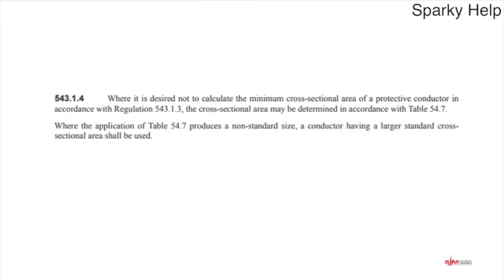Where it is desired not to calculate, and I think most of us would prefer not to calculate if required, the minimum cross-sectional area of the protective conductor in accordance with 543.1.3, the cross-sectional area may be determined in accordance with Table 54.7. Where the application of Table 54.7 produces a non-standard size, a conductor having a larger cross-sectional area shall be used. And I would say probably most electricians out there would know how to size an earth, and they probably won't need to look this table up, they would probably just know it.